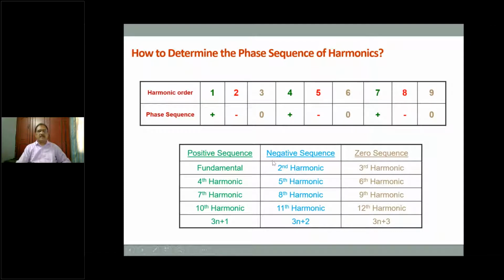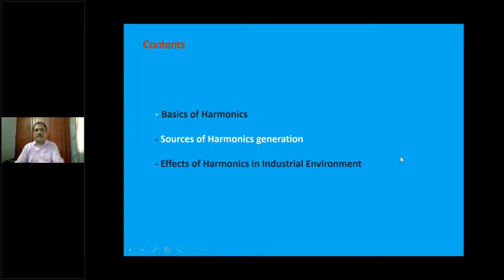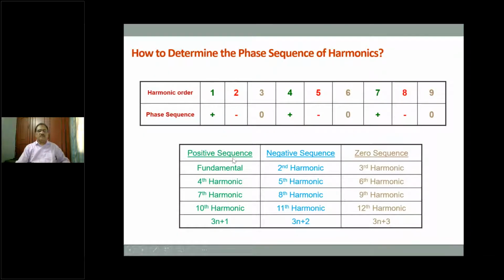As you can see here at the bottom, the positive sequence will be the fundamental, 4, 7, 10, and so on; orders of 3 plus 1 will be called positive sequence. Negative sequence will be 2, 5, 8, 11; orders of 3 plus 2. Zero sequence will be 3 and multiples of 3. Typically, we will measure odd multiples of 3. That means 3 into 3, 9, 3 into 5, 15, 3 into 7, 21, 3 into 9, 27. These are all called triplen or zero sequence harmonics.